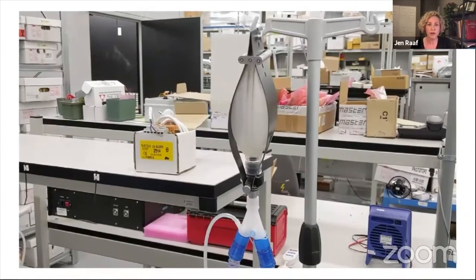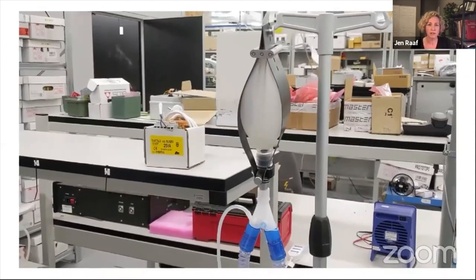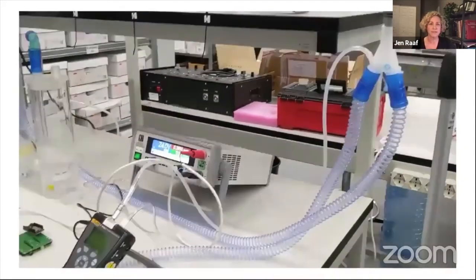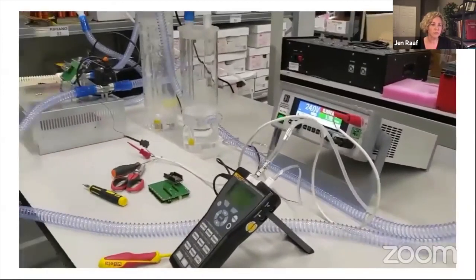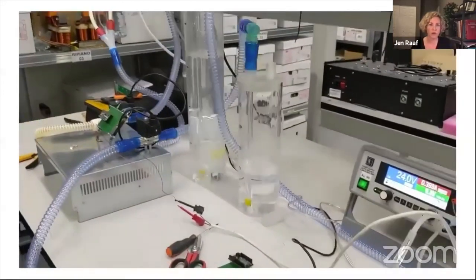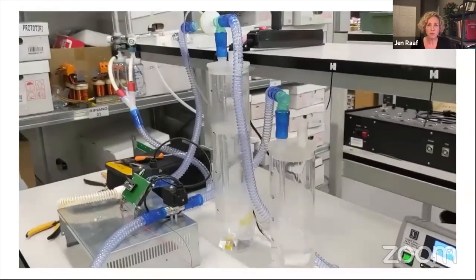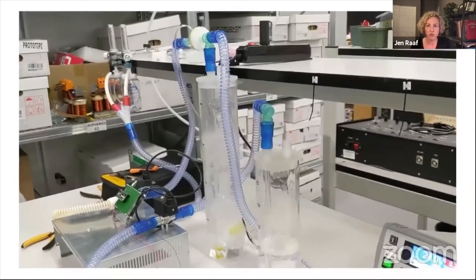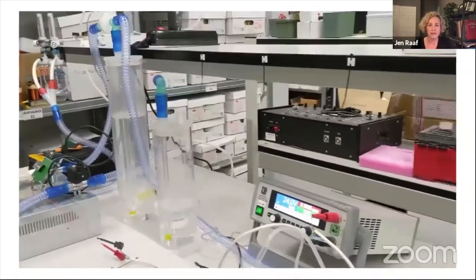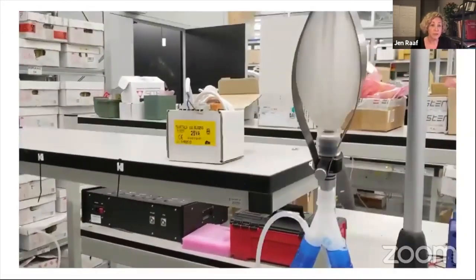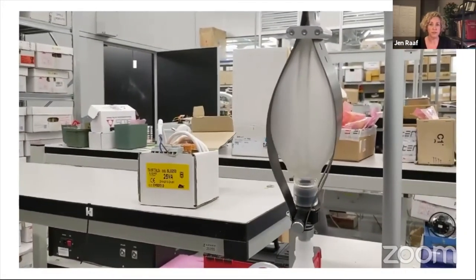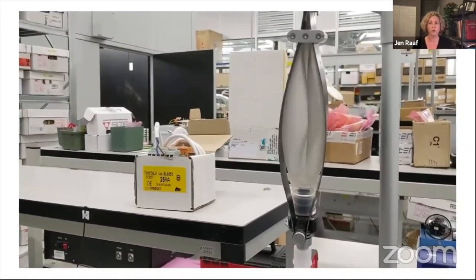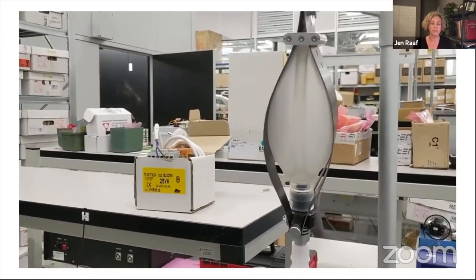What you're looking at right now is actually a fake lung to let us test the functionality of the device. The tubing is what's providing the air direction and flow, and those columns of water are just a way of regulating the pressure. Those are definitely not intended to be in the final design, but this was just a proof of concept to see that we could make our microcomputer do the correct sequencing of inhalation and exhalation on the right time scale.